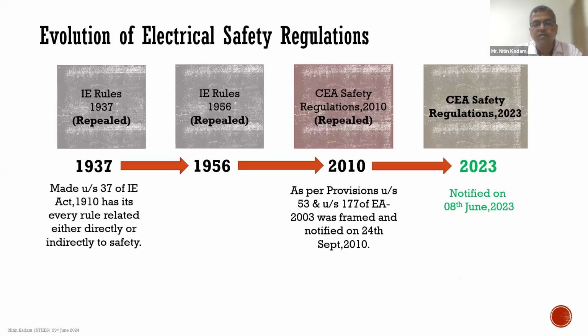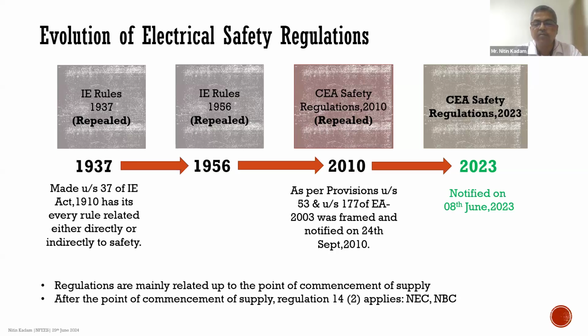So if you see here, this is how the regulations have evolved in India. We had the Indian Electricity Rules 1937, followed by the rules in 1956, followed by the CEA regulations in 2010. And now we have the latest regulation, the CEA Safety Regulations 2023, which was notified on 8th of June 2023. So please refer to the latest regulation. The earlier regulations have been repealed. Please do not refer to those. This is my sincere request to all of the audience here. The regulations mainly relate up to the point of commencement of supply, and after the point of commencement of supply, according to Regulation 14, the NEC or the NBC applies.